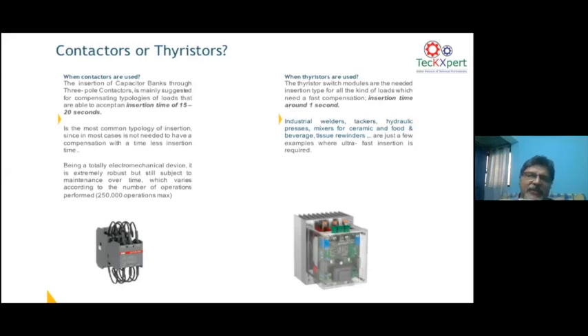The second thing is, whenever you connect a capacitor to the grid, if you look at the voltage waveform and you connect the capacitor at 0 volts, there won't be any current flowing into the capacitor. There won't be any surges. That means in thyristor switching, you try to close at 0 volt. When the voltage waveform is at the 0 point, you switch on the capacitor bank. There is no inrush current, so you will not get an over voltage.